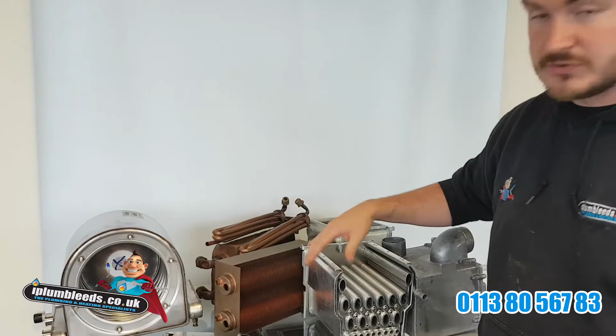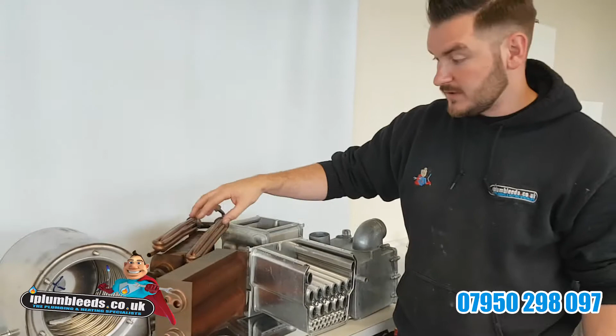The older versions were copper, so back in the day with non-condensing boilers, you'd have a copper heat exchanger. Copper heat exchangers are really good at transferring heat, but due to condensing boilers now, the condensation is acidic, so we can't use copper as much as we'd like nowadays. So we now use stainless steel and aluminium, which gets me onto this heat exchanger.